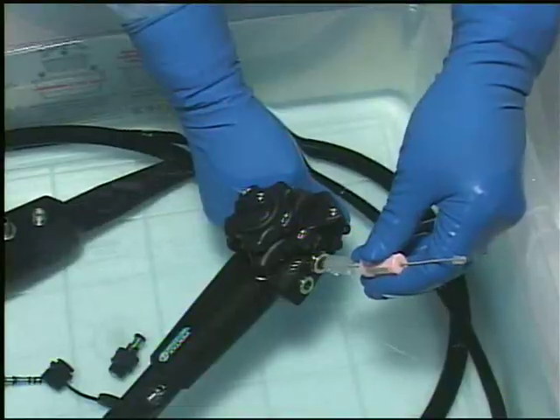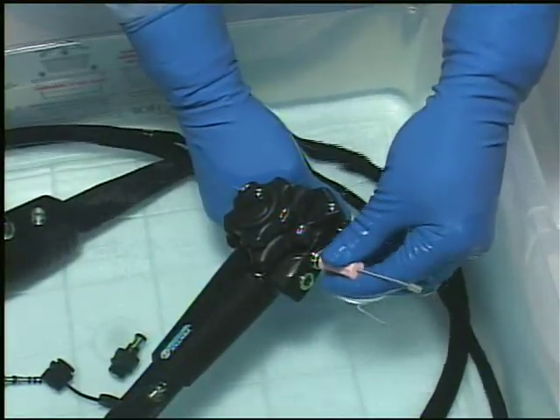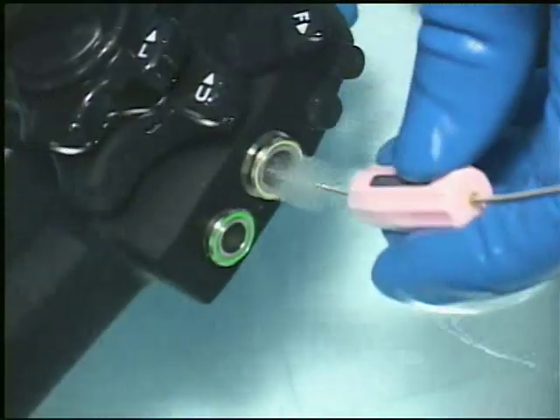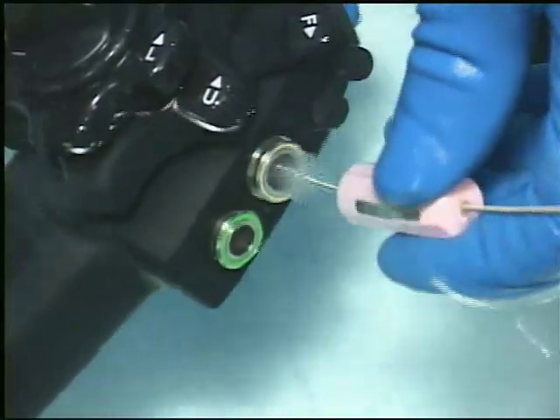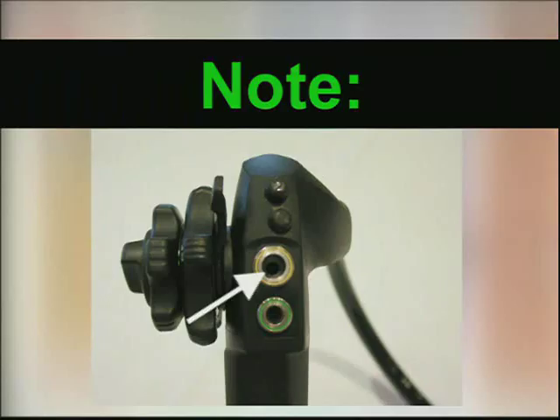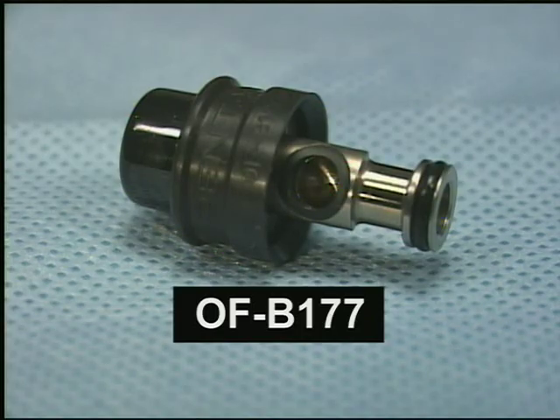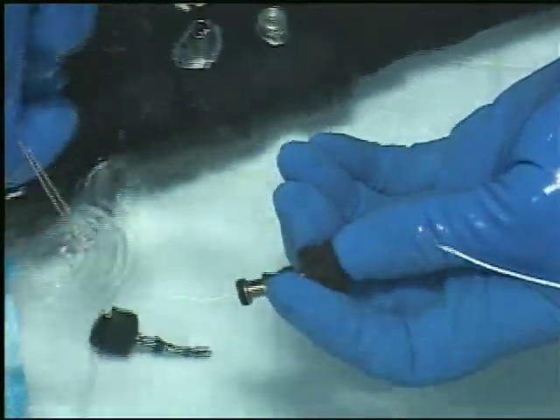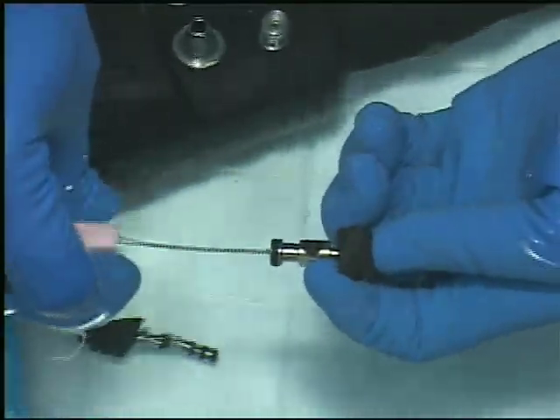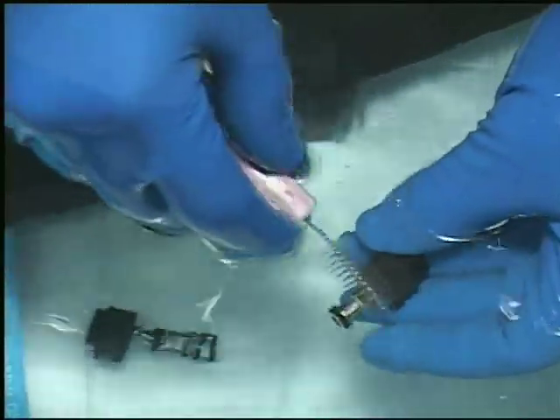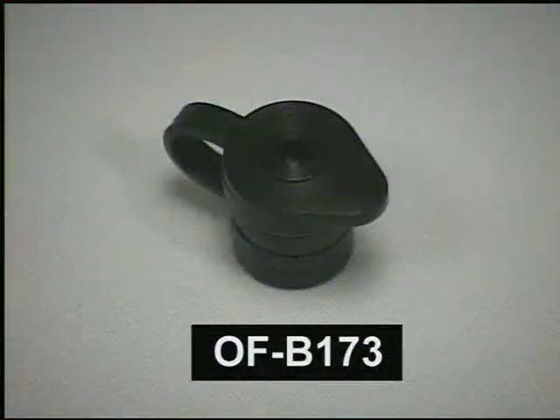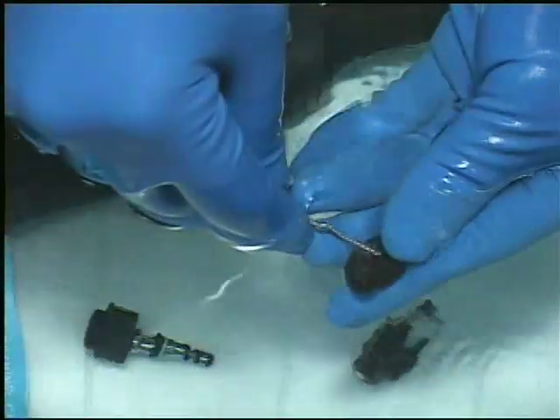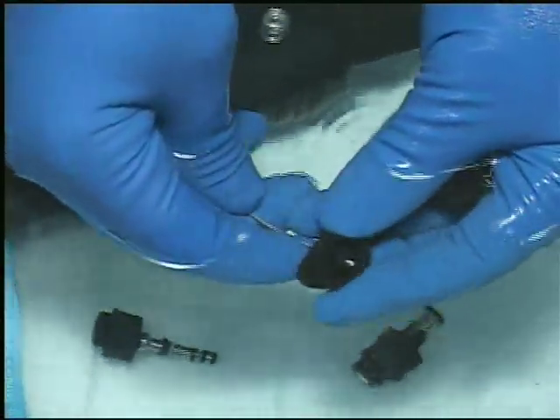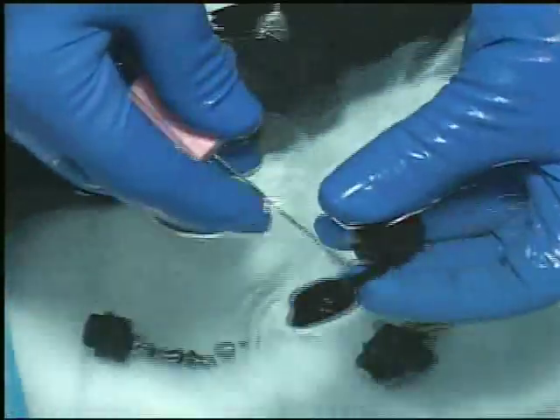Using the large bristle of the cleaning brush CS-C8S, scrub clean the surfaces inside the suction control valve receptacle on the control head. Note: Be sure to inspect the bottom of the suction control valve receptacle for any debris. Scrub all internal and external surfaces of the suction valve OFB177 using the smaller side of the cleaning brush CSC8S. The rubber inlet seal OFB173 should be disassembled and all surfaces brushed with the CSC8S cleaning brush.